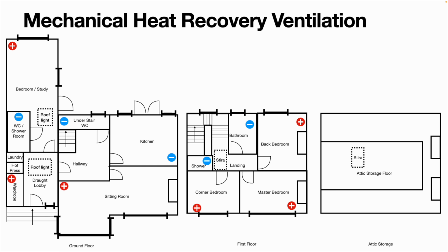If you tot it up, you'll see that roughly speaking the quantity of inlets and outlets matches up, and that's deliberate. You want a balanced system generally speaking - as much air going into the house as is being taken out. You don't want the house running at negative pressure, and similarly you don't want the space over-pressurized. In most cases you want balanced air.